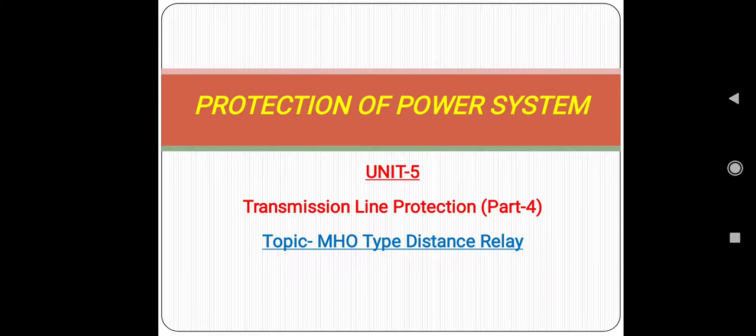In an earlier lecture I told you some drawbacks occur in reactance type distance relay. The reactance relay is basically not capable of discriminating the faults which occur either in the protected zone or outside the protected zone. Therefore the reactance type distance relay needs a directional unit that is inoperative under normal load conditions.